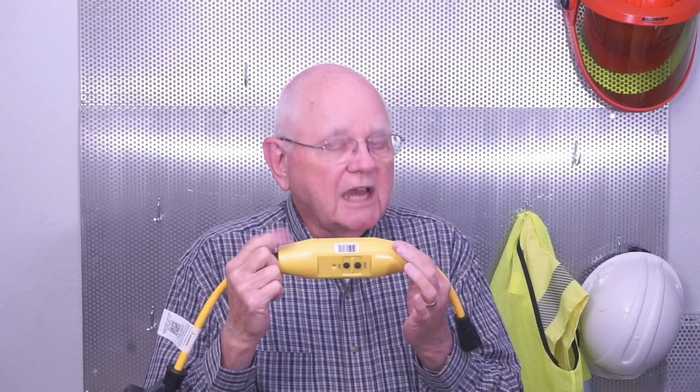One is very common on a job site. We're going to use GFCIs, aren't we? So a pigtail like this. Got the attachment plug on one end, the other end's a receptacle end, but in the middle, I've got my GFCI, ground fault circuit interrupter. It's going to trip somewhere between 4 and 6 milliamps in order to protect me on the job site. I plug it in, it trips, that's my self-test for it, then I reset it, and off I can go to work.